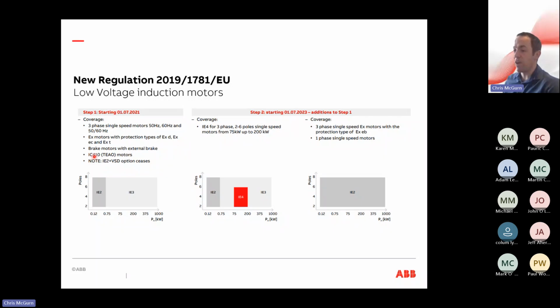And there used to be a way of getting around it where if you used an IE2 motor with a VSD, you could continue to use your IE2 motor. However, you're not supposed to do that anymore. The requirement is to use IE3 or IE4, depending on what your kilowatt size is. So it's a requirement. It's been pushed by the EU. Overall, the intention is to improve efficiency in the long run.